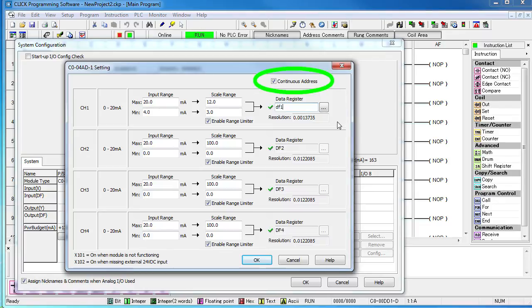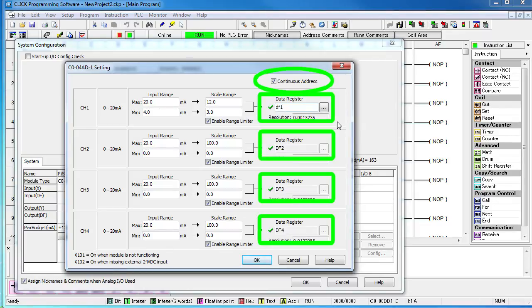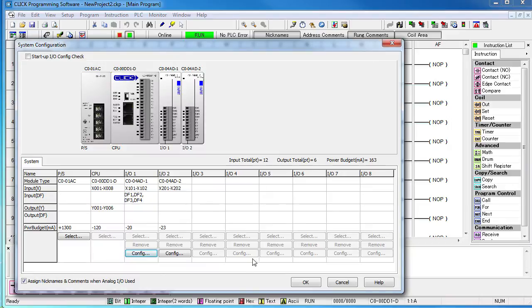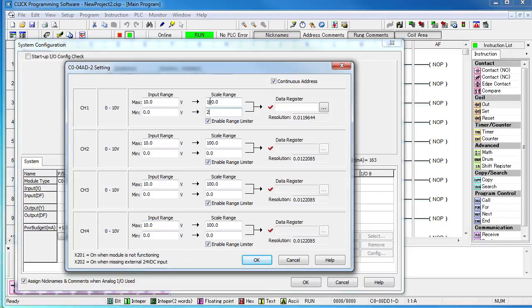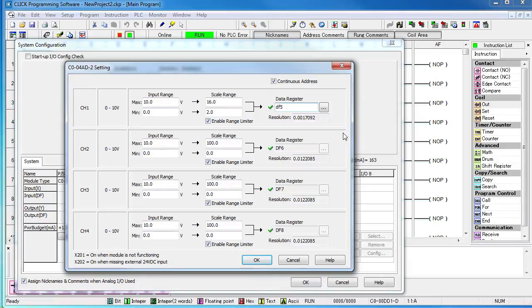Because this continuous address is selected, the software automatically assigns DF2 through DF4 to these guys even though we are not using them. So when we do the voltage input module, which will run from 0 to 10 volts, which represents 2 to 16 inches, we need to put that result in DF5, the next available location.